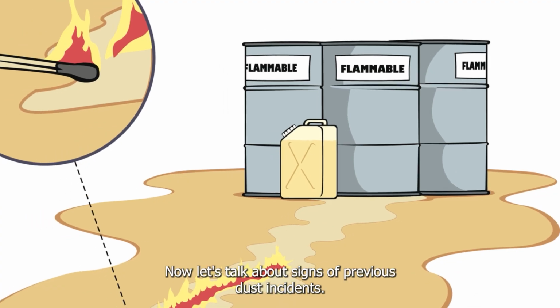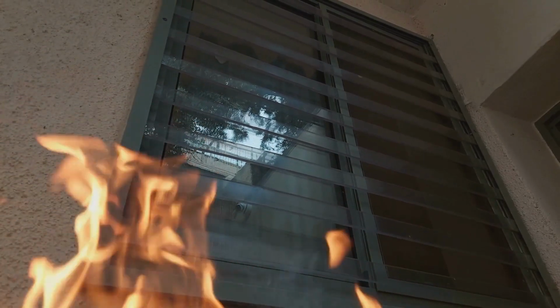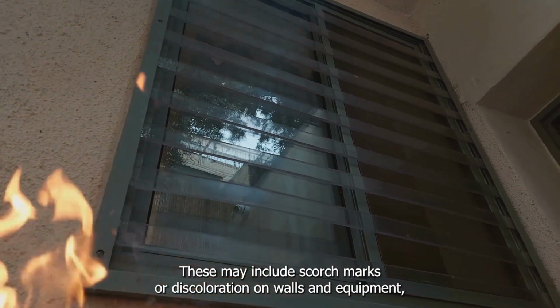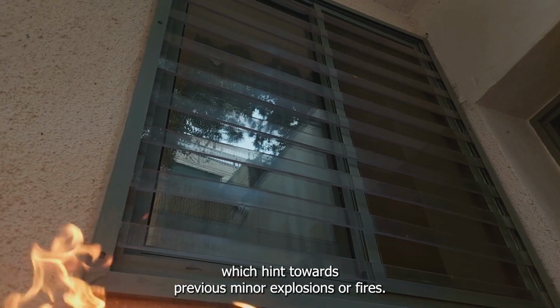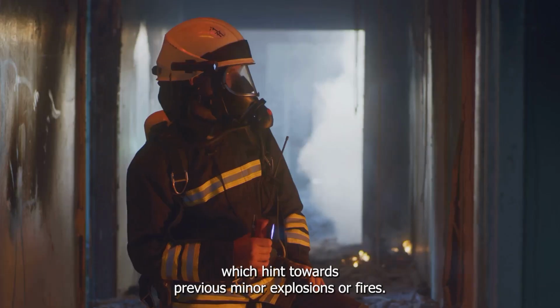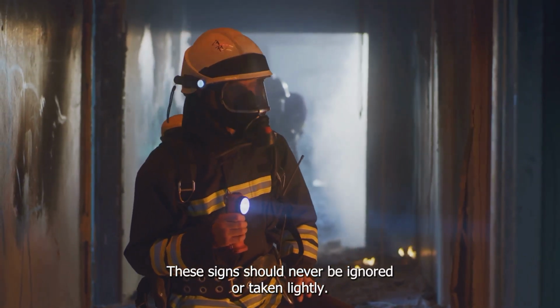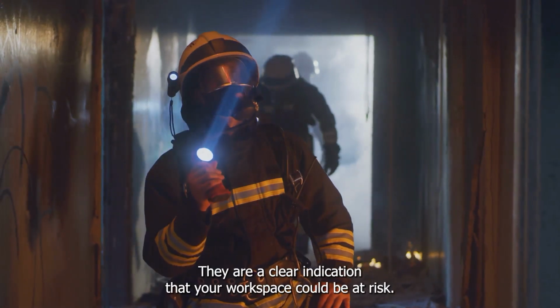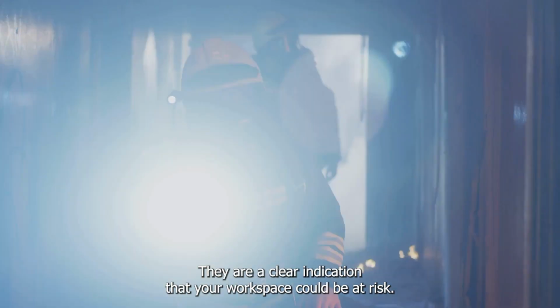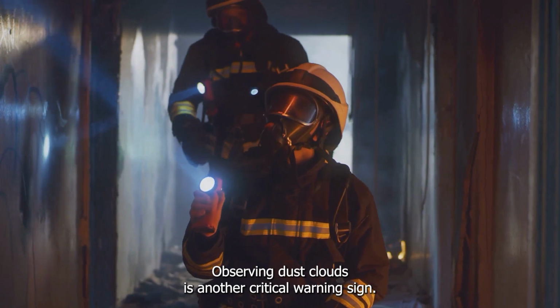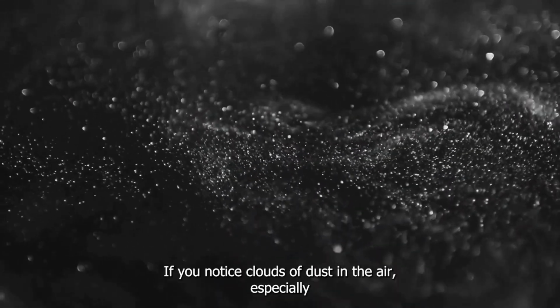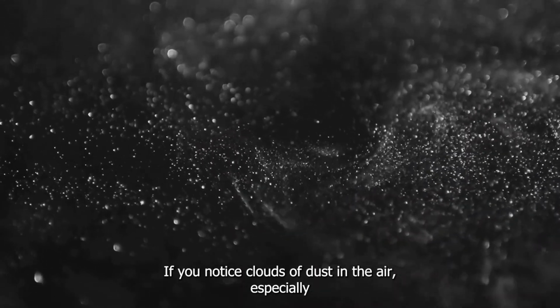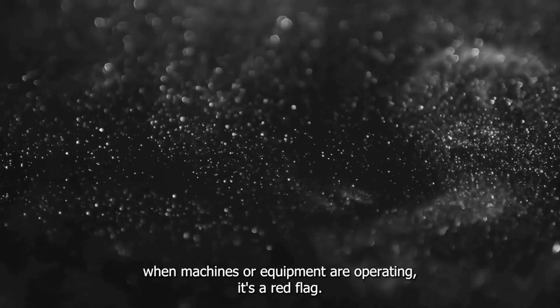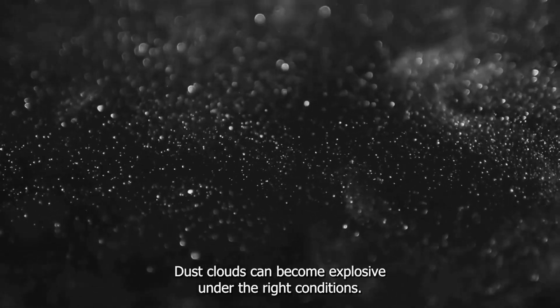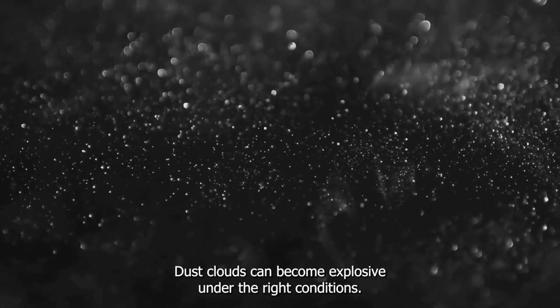Now let's talk about signs of previous dust incidents. These may include scorch marks or discoloration on walls and equipment which hint towards previous minor explosions or fires. These signs should never be ignored or taken lightly. They are a clear indication that your workspace could be at risk. Observing dust clouds is another critical warning sign. If you notice clouds of dust in the air, especially when machines or equipment are operating, it's a red flag. Dust clouds can become explosive under the right conditions.